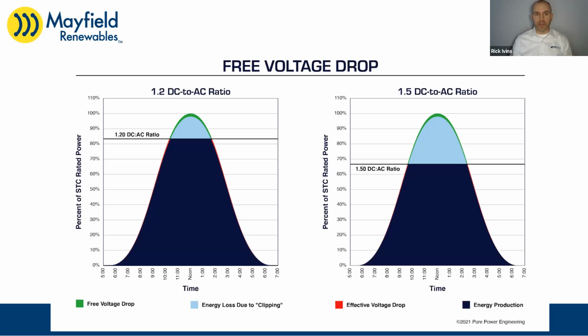The area in green is that free voltage drop you can get, and obviously the higher DC to AC ratio has more green to it. Looking below the line is important too, because that's the voltage drop that does start the cost. You can barely see the red sliver in both of these—that's because it's pretty small. At STC, if you're at 100% STC, that's full output or more or less. All the levels below clipping are not at STC, and your voltage drop really drops quickly below there, actually exponentially decreasing. So you have a lot less voltage drop down low—voltage drop is a bigger issue at the higher levels of output.